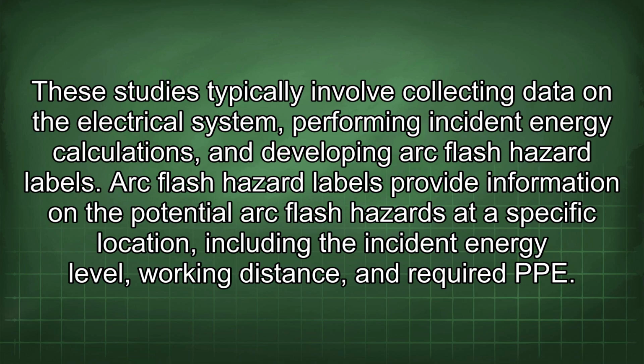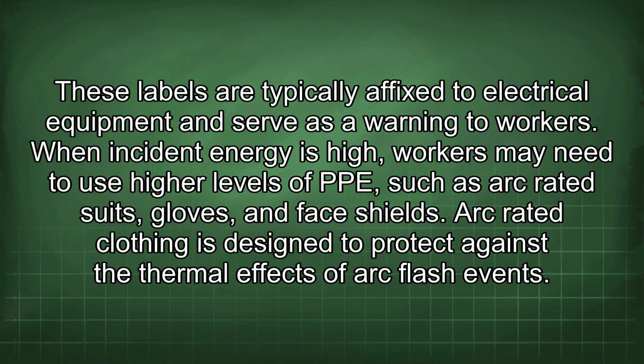Arc flash hazard labels provide information on the potential arc flash hazards at a specific location, including the incident energy level, working distance, and required PPE. These labels are typically affixed to electrical equipment and serve as a warning to workers. When incident energy is high, workers may need to use higher levels of PPE such as arc-rated suits, gloves, and face shields. Arc-rated clothing is designed to protect against the thermal effects of arc flash events.